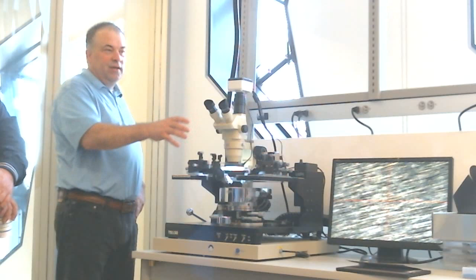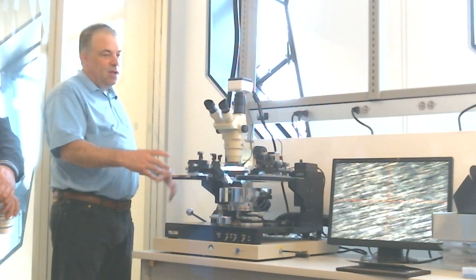You can purge that one too, if you want to purge it with nitrogen, if we've got oxygen sensitive devices as well. So that one is also a probe station. Yes, they're nearly the same, but that one is a little bit bigger. This one's 150 millimeter, that's 200 millimeter. But the main thing with that one is an enclosed chamber. It's primarily for EMI shielding, but you can also do temperature testing with it as well. So it isolates everything.